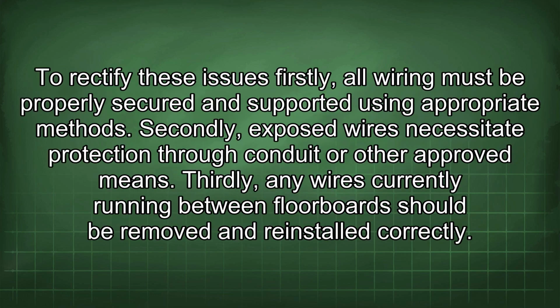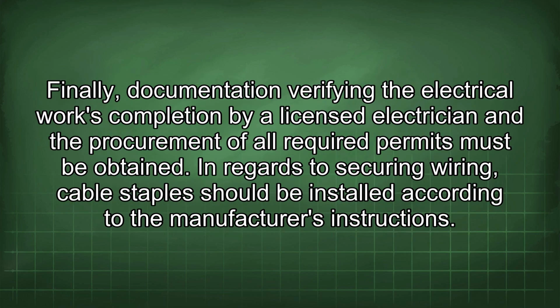To rectify these issues, firstly, all wiring must be properly secured and supported using appropriate methods. Secondly, exposed wires necessitate protection through conduit or other approved means. Thirdly, any wires currently running between floorboards should be removed and reinstalled correctly. Finally, documentation verifying the electrical works completion by a licensed electrician and the procurement of all required permits must be obtained. In regards to securing wiring, cable staples should be installed according to the manufacturer's instructions.